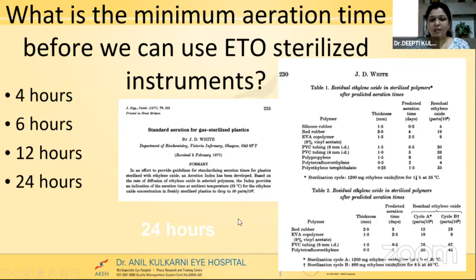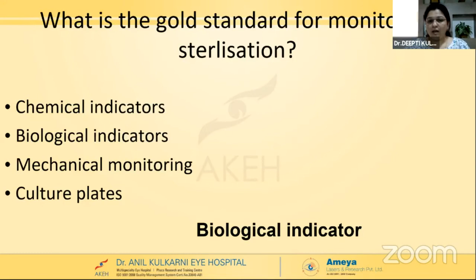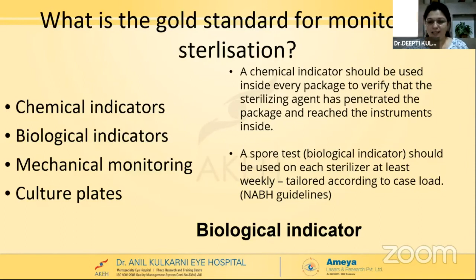The next question is, what is the gold standard for monitoring of our sterilization? We check the sterilization using the chemical strip or chemical indicators, the strip that we place on the outside of our sets when we sterilize. But how do we monitor our sterilization? The answer here is a biological indicator. What should be the frequency? NABH does recommend weekly evaluation, although based on the load, weekly, fortnightly, or monthly can be done, but weekly and fortnightly are the most recommended in most guidelines that I could come across.